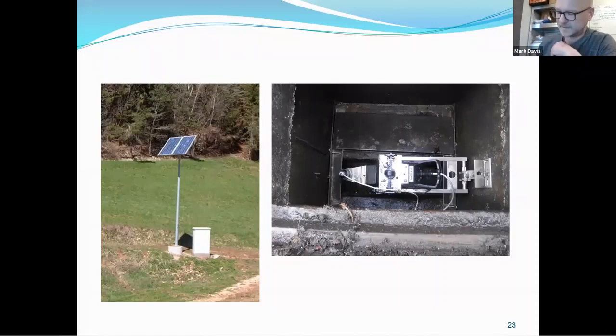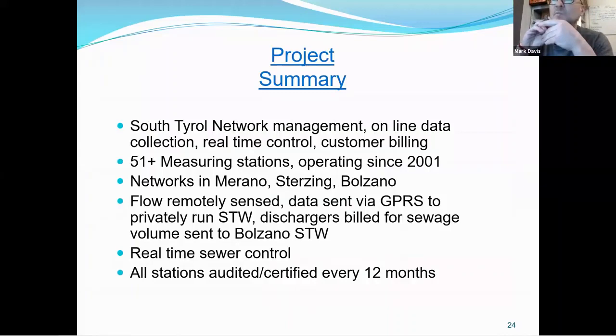So again, operating since 2001, used for real-time control. The controller can select an individual measuring site. There are powered penstocks, control gates, on each of these measuring sites, and he can set a maximum flow and leave the system to do closed loop flow control.